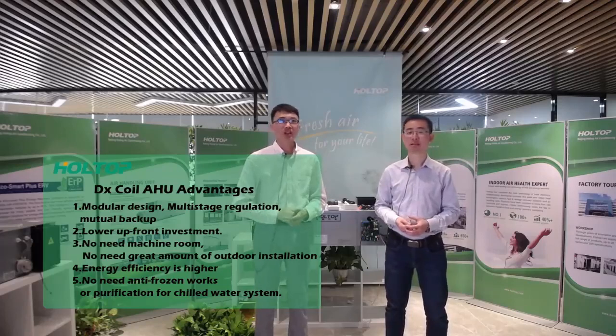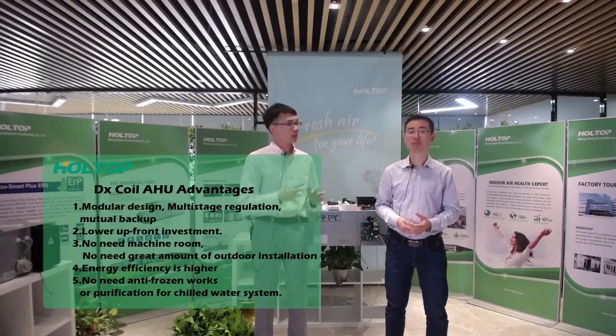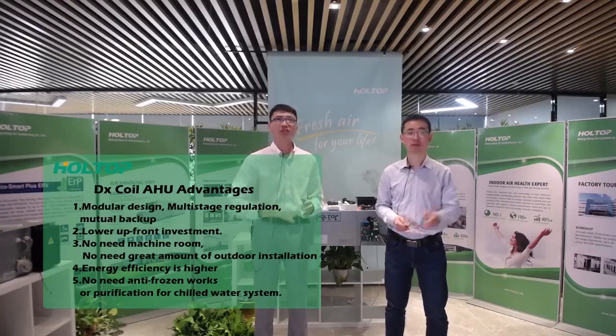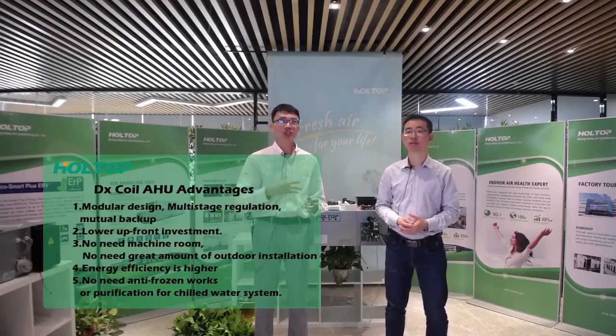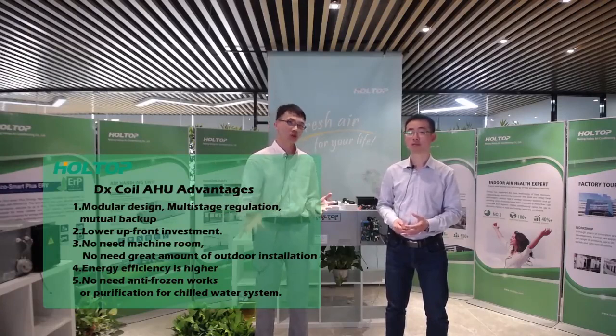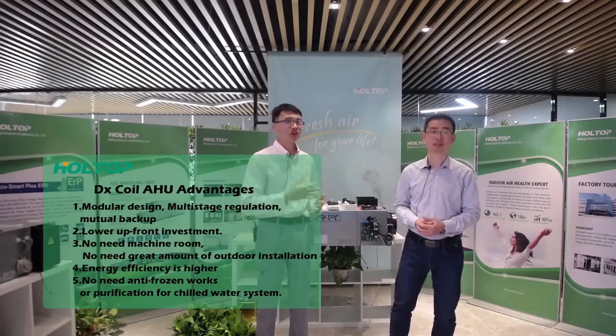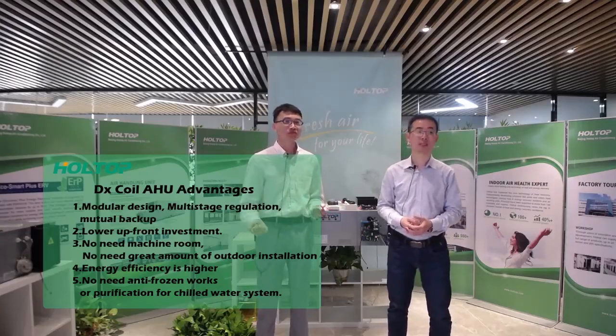Number three, no need for a machine room and no need for a great amount of outdoor installation works. The condensing unit is designed for outdoor use, and besides, now there is no chilled water system or pump. The machine room is not required, and the installation becomes very easy.